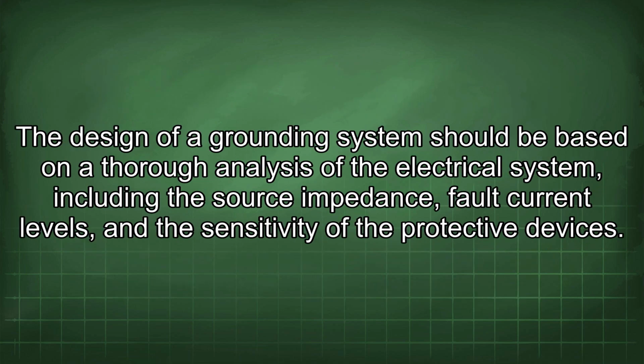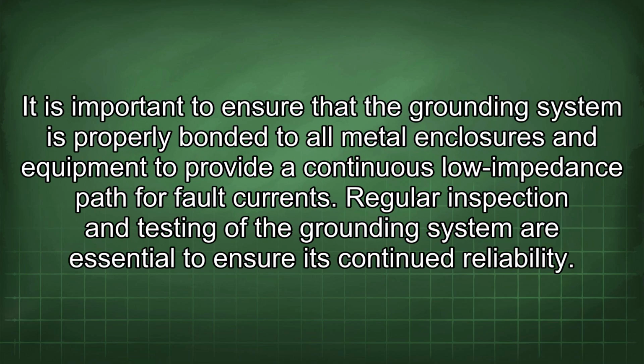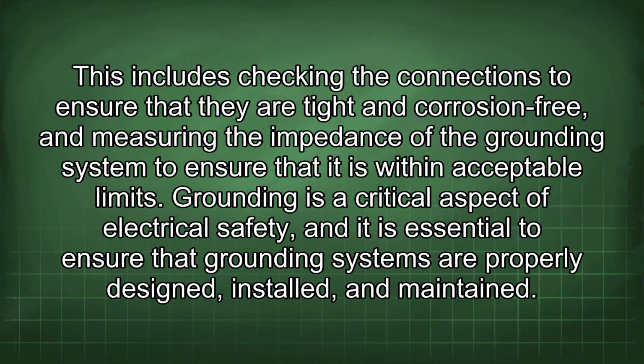The design of a grounding system should be based on a thorough analysis of the electrical system, including the source impedance, fault current levels, and the sensitivity of the protective devices. It is important to ensure that the grounding system is properly bonded to all metal enclosures and equipment to provide a continuous low impedance path for fault currents. Regular inspection and testing of the grounding system are essential to ensure its continued reliability. This includes checking the connections to ensure that they are tight and corrosion-free, and measuring the impedance of the grounding system to ensure that it is within acceptable limits. Grounding is a critical aspect of electrical safety, and it is essential to ensure that grounding systems are properly designed, installed, and maintained.